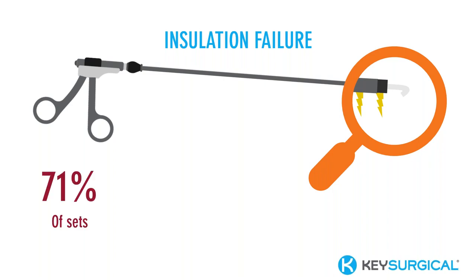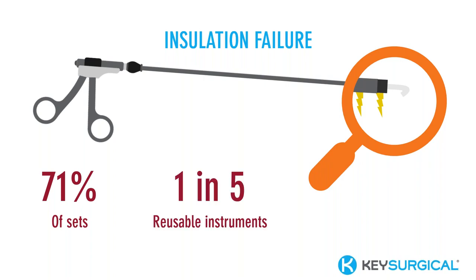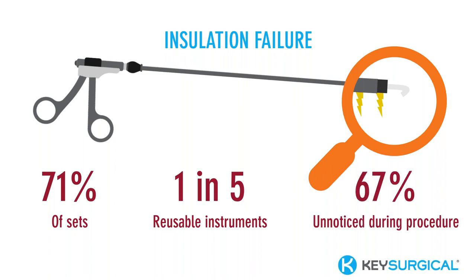When reusable sets were evaluated, so reusable laparoscopic instruments, 71% of the sets had at least one instrument with insulation failure. So that's well over half. And as a broad statistic, they found that 1 in every 5 reusable laparoscopic instruments has an insulation failure. Now, to further complicate all of this, other research, not from this study, shows that 67% of stray electrosurgical burns go unnoticed during the procedure, so during surgery. Various statistics clearly identify the seriousness of these complications, which can be as small, using that very loosely, as an extended stay in the ICU after surgery, to as big as causing death in about 25% of the patients that suffer these complications when they aren't noted at the time of the procedure.